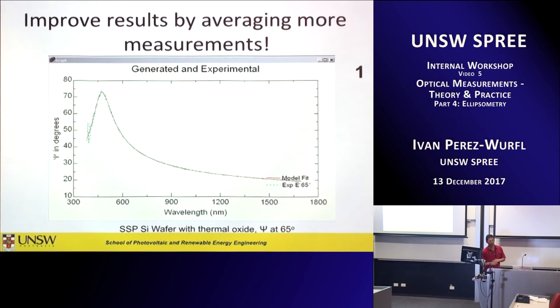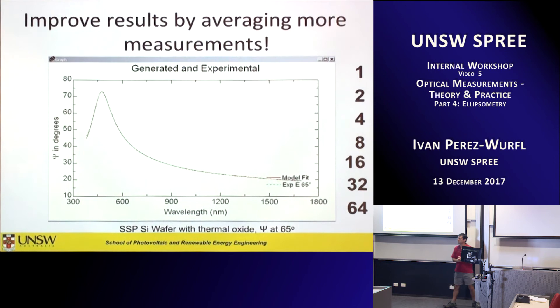One thing that is easy to demonstrate compared to R and T is how much better measurements get as you average more. On the ellipsometer, it takes about a fraction of a second to do one measurement, so you can very quickly see how clean your measurements become going from 1 to 64 averages. I'm not going to have time to show you everything you could do with WVASE and ellipsometry, except to show you that the models Ned talked about are naturally available there.